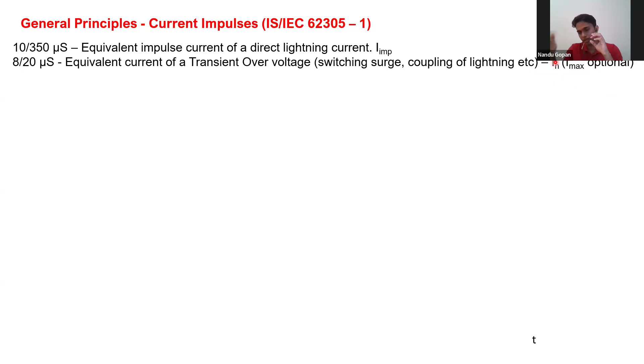And you can also see in a class 2 tested SPD, it is very common in India. If you check that label also, it will be tested for I nominal, and sometimes optionally for I max. For I max, they are putting an 8 by 20 microsecond strike. They are putting it one maximum time, and they are checking how much it can withstand. I nominal means it will be applied repeatedly as per the SPD standard requirements. So it will be multiple strikes at I nominal.